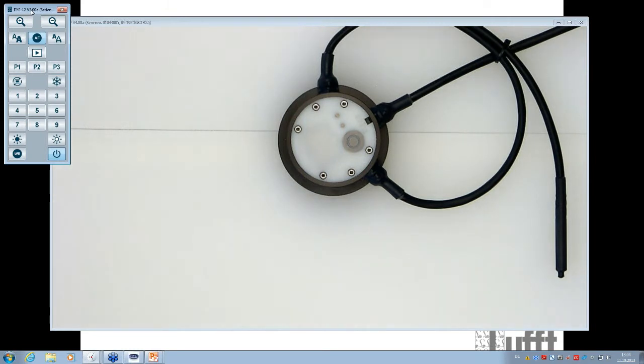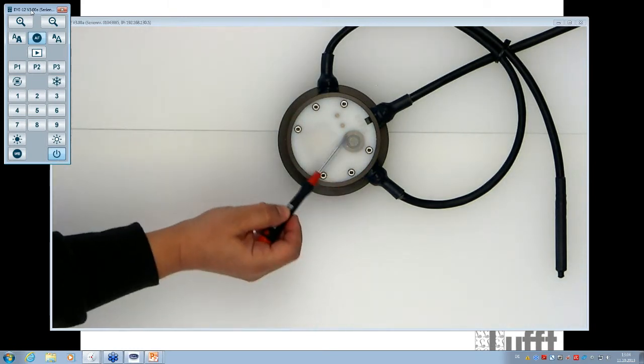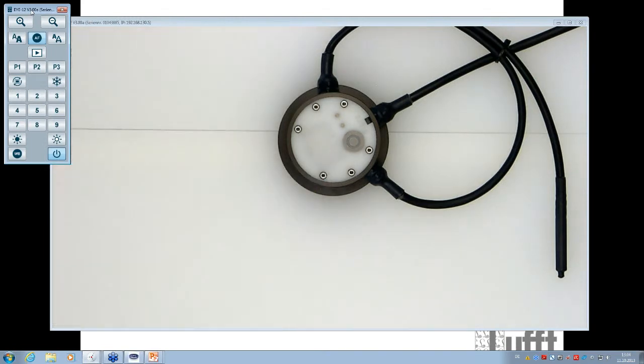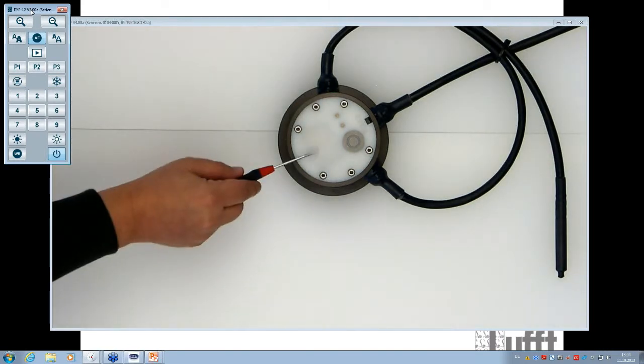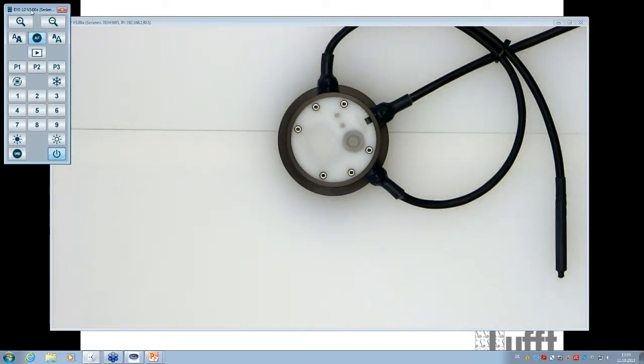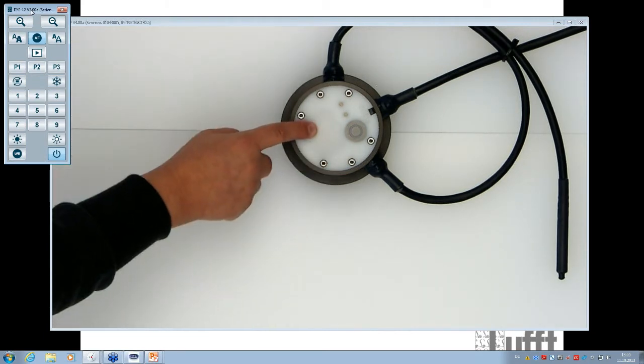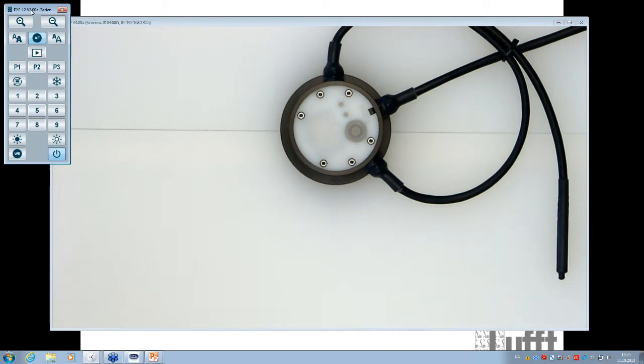No, it will not measure, because we have an additional measurement here with the two steel electrodes. This is an internal measurement. It will not be shown as an output, but it is used to regulate or to activate this radar sensor. Why? It's easy. Think about, maybe you will have a leaf or an insect running here on the surface. That means if there is something which is not water lying on the surface, this will be a reason to show a water film. And of course this is not a thing the customers want to have.